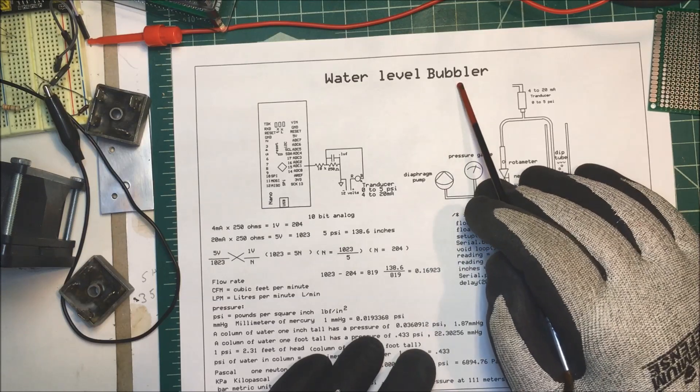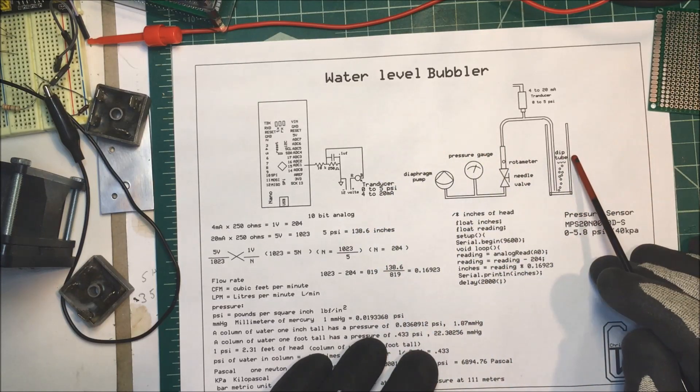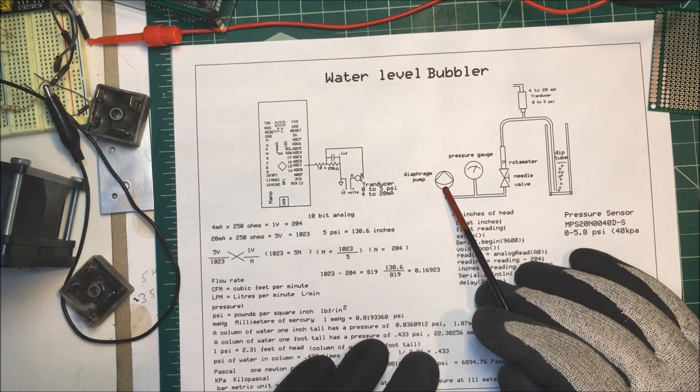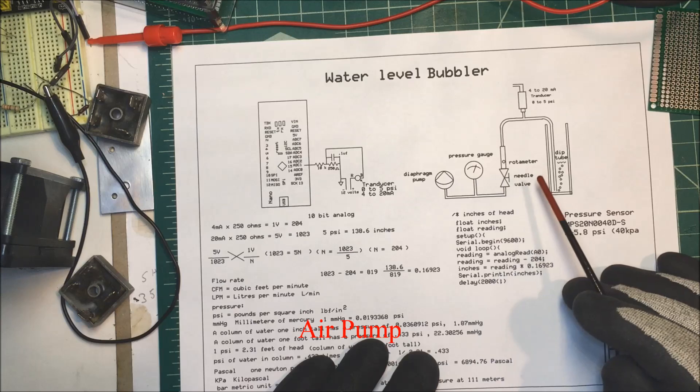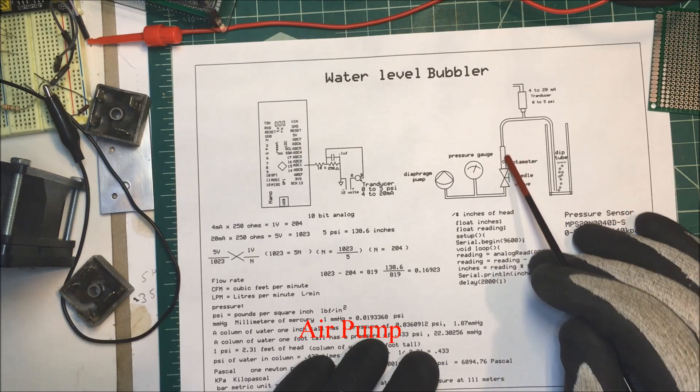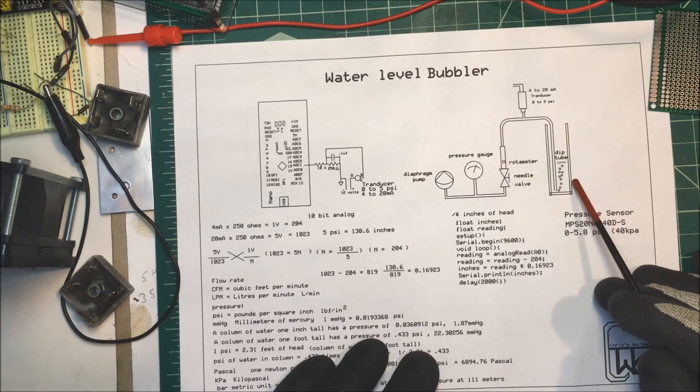Let's take a look at a bubbler system. We're going to use it to determine the water level, whether it's in a well or in a tank. In order to do that, we just have a pump and then a pressure gauge. We have a needle valve and a rotometer here that we can control the flow of air into this dip tube down in here.